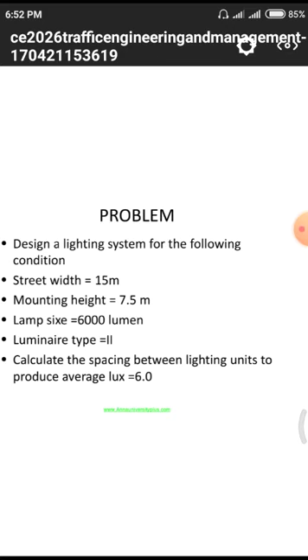This is the design example problem. What are the terms associated with these lighting parameters? First of all, the total street width is 15 meters. The mounting height, normally we go for 6 meters, but here we have a height of 7.5 meters, and the size of the lamp is 6000 lumens. Luminaire type is type 2. Calculate the spacing between the light units to provide an average lux equal to 6.